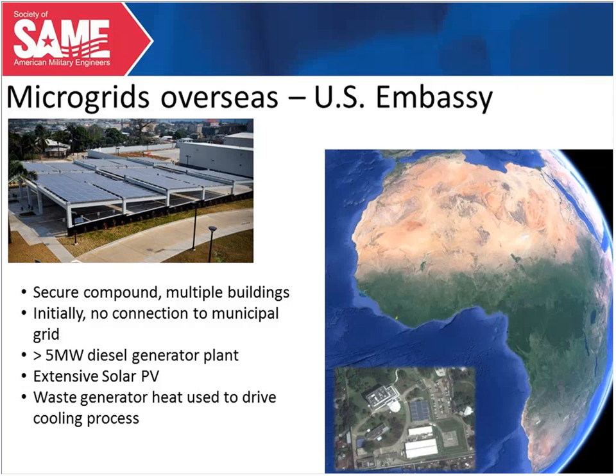So this was pretty much an off-grid application, a complete microgrid. We had several buildings, and a diesel generator plant that was all tied together to form a microgrid. We integrated it with extensive solar PV, which took load off the generator and saved a considerable amount of fuel. We also used the waste heat from the generators to drive a cooling process, which further helped with efficiency.